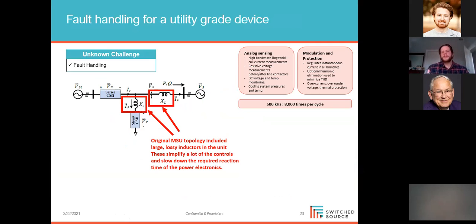One of the things we really struggled with is fault handling, and understanding that when you're out on the distribution grid, there's voltages, power quality, and abuse you're going to potentially take from things like lightning, where surge arresters kick in. If you're just exposing your system directly with power electronics, to even have a shot in the dark of surviving for a long period with all the faults you're going to see out on the grid, you have to control your device fairly quickly.